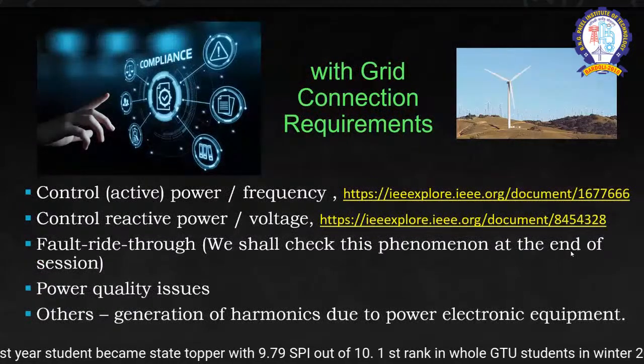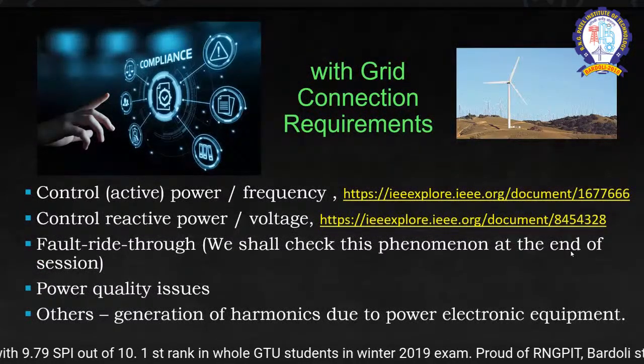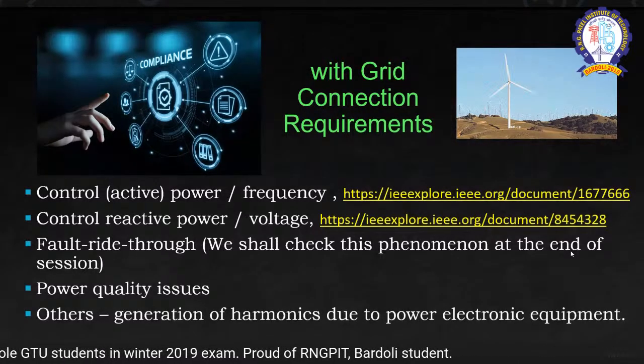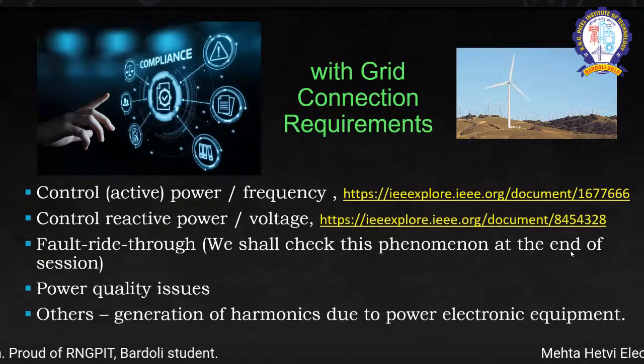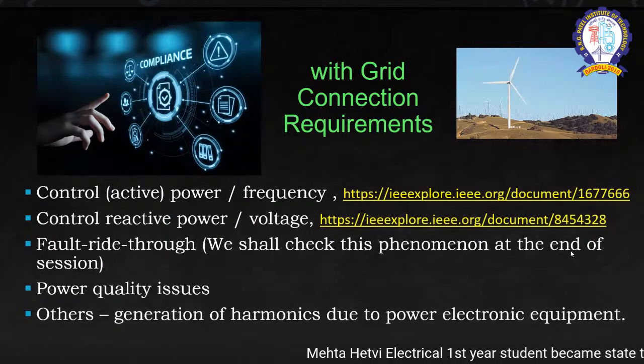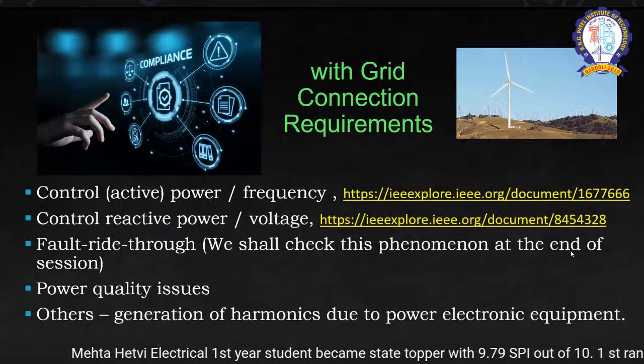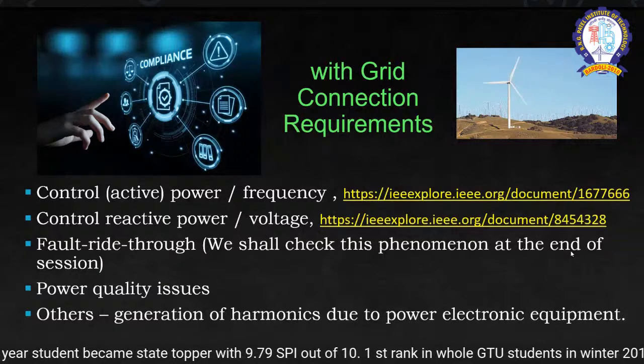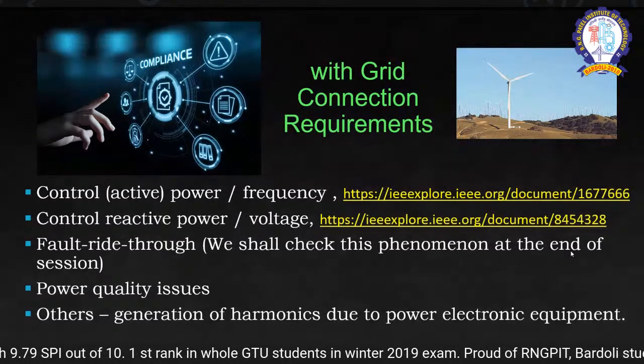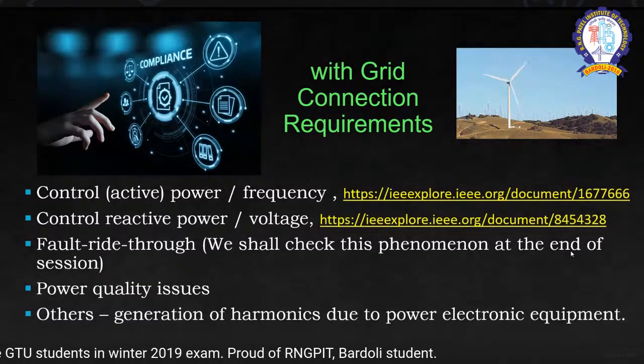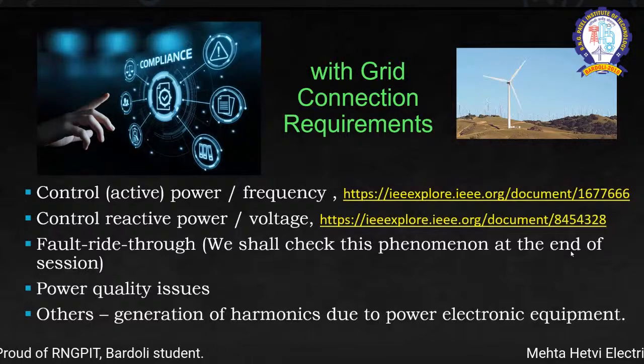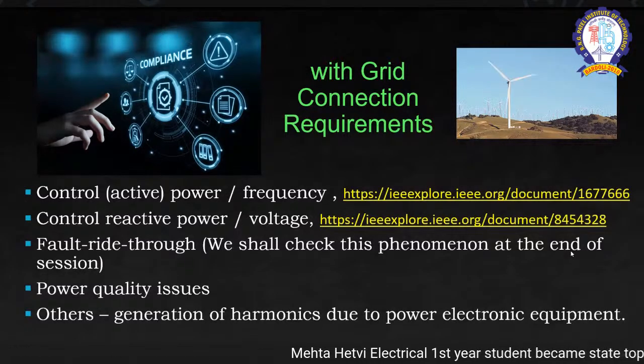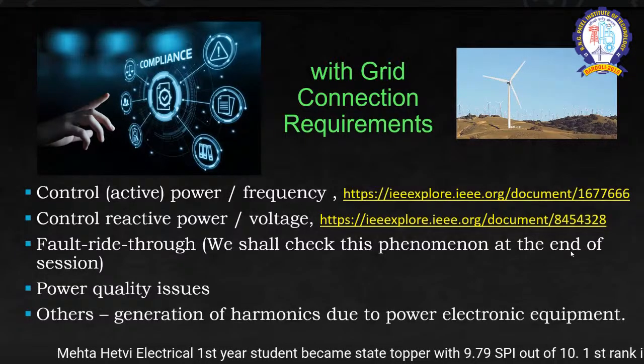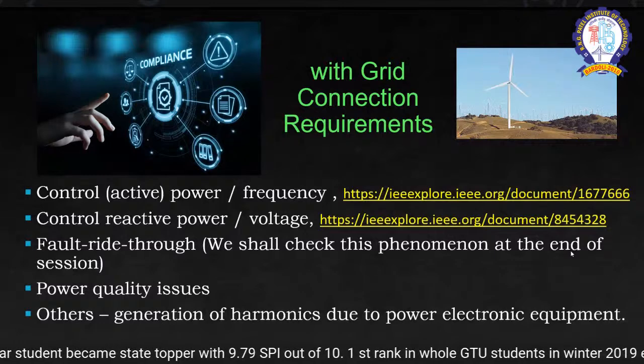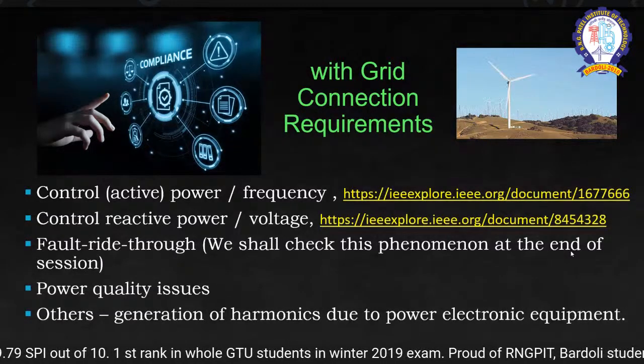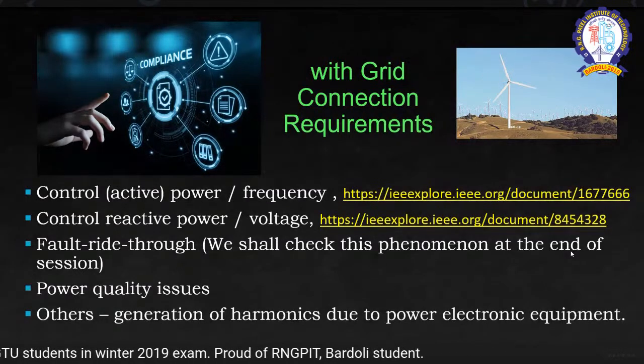So with grid connection requirements, what do we need to control? First, active power, which is related to the frequency. There is one more document available. In this document, you will be able to observe how we can control this active power. Second is the reactive power, which is related to the voltage. If you can control this reactive power, you can easily control the voltage at the terminal end of the PCC, the point of common coupling. One more document is there if you need to explore. Whenever I share this PPT, this link will be shared with all the audience, so you can gain extra and additional knowledge for controlling these electrical parameters.